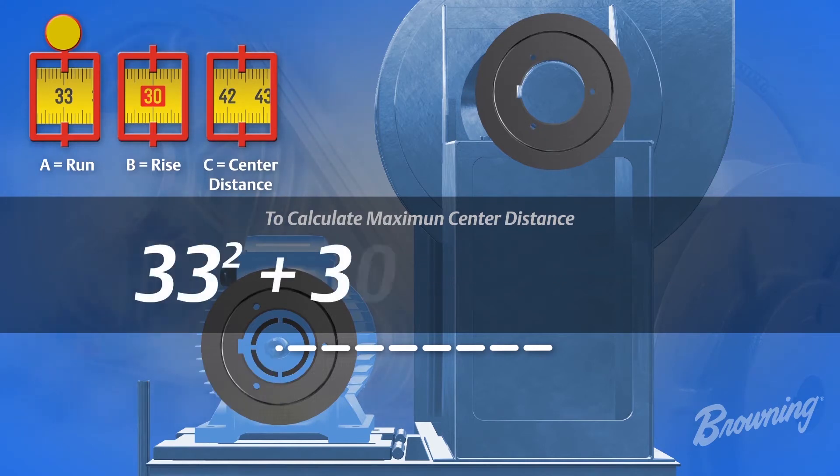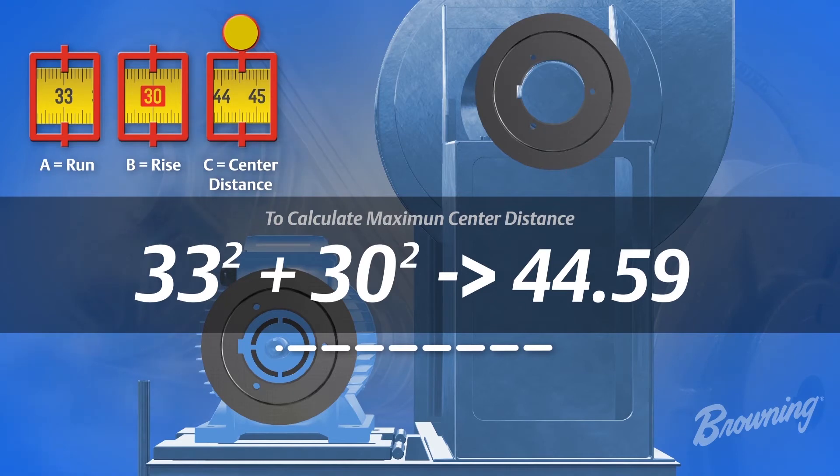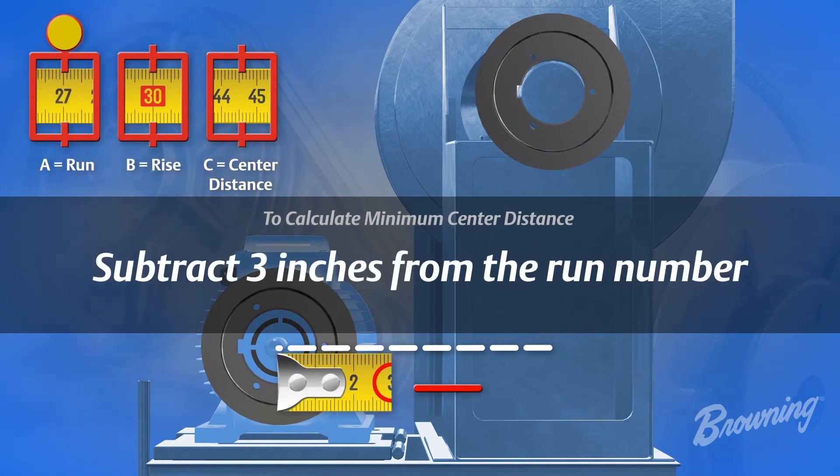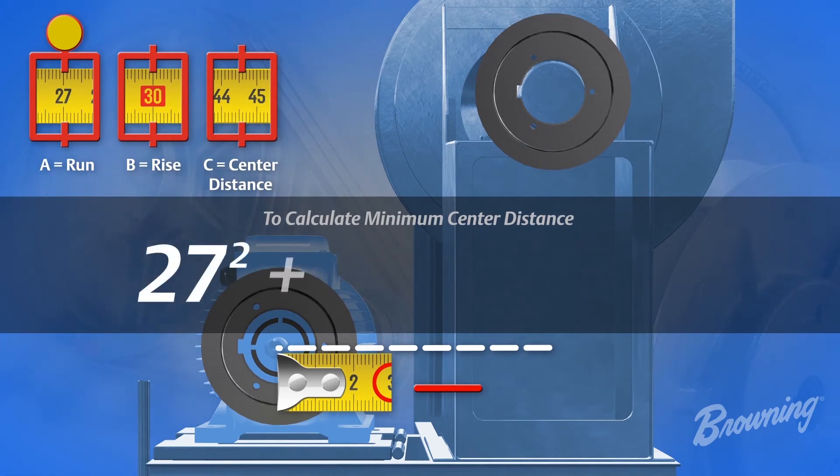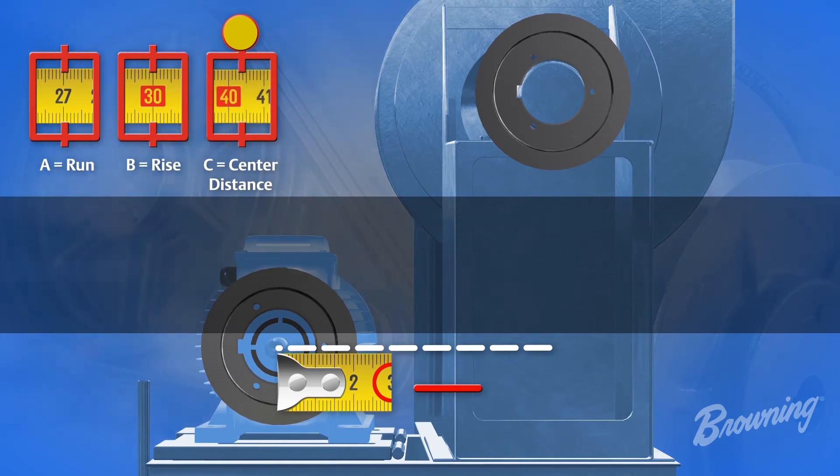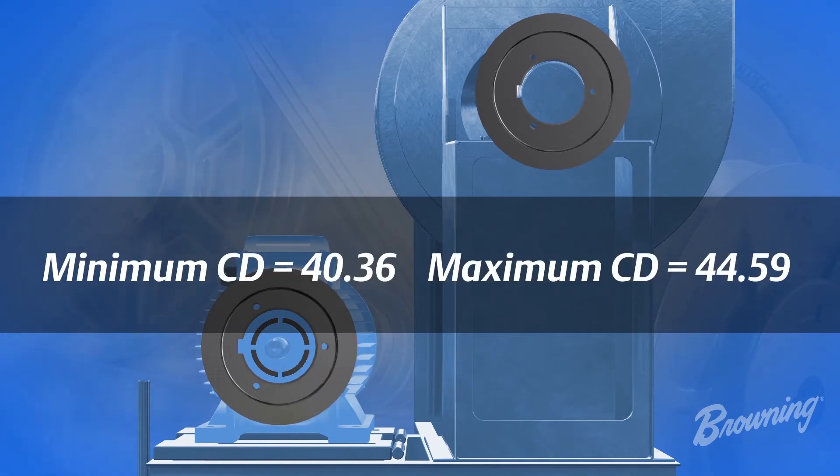To calculate minimum center distance, we would subtract 3 inches from the run number and make it 27. 27 squared plus 30 squared equals 40.36. So our minimum and maximum center distance numbers are 40.36 and 44.59.